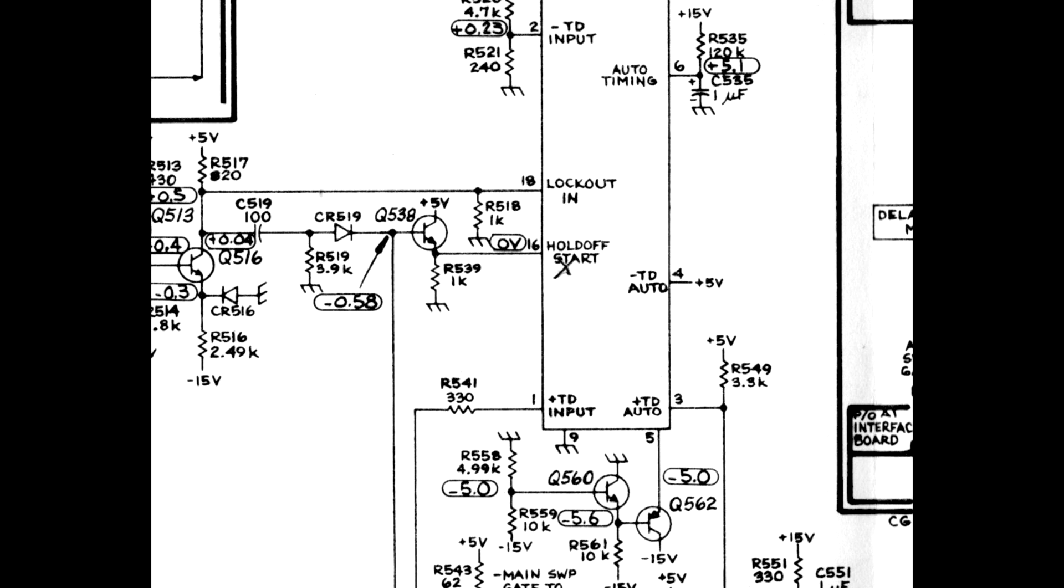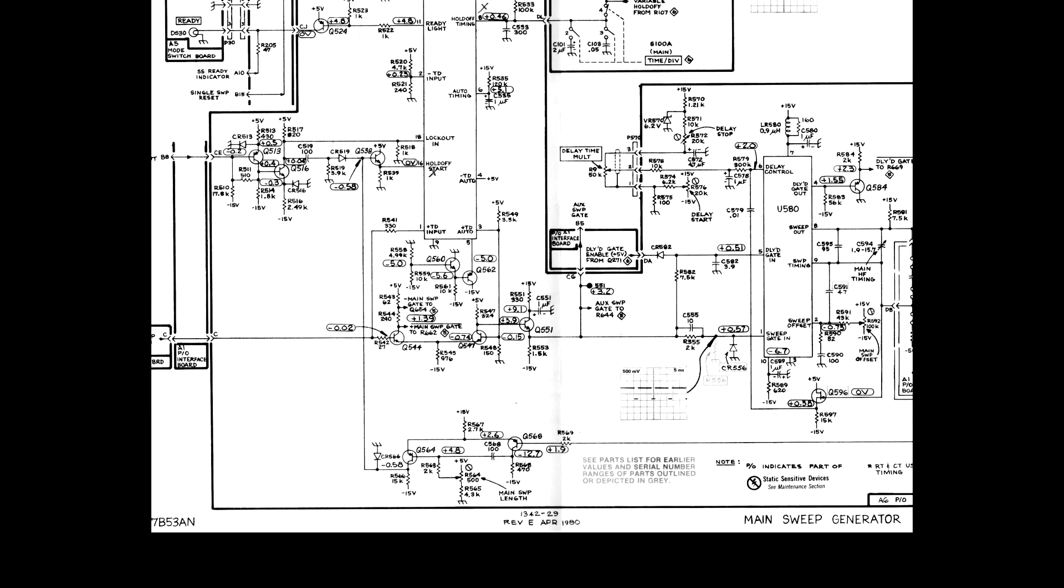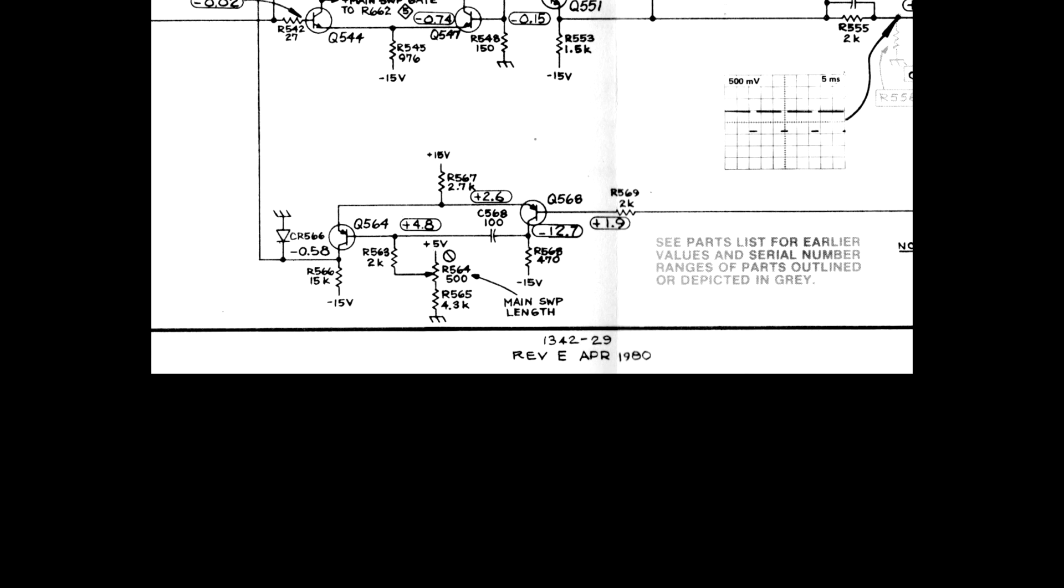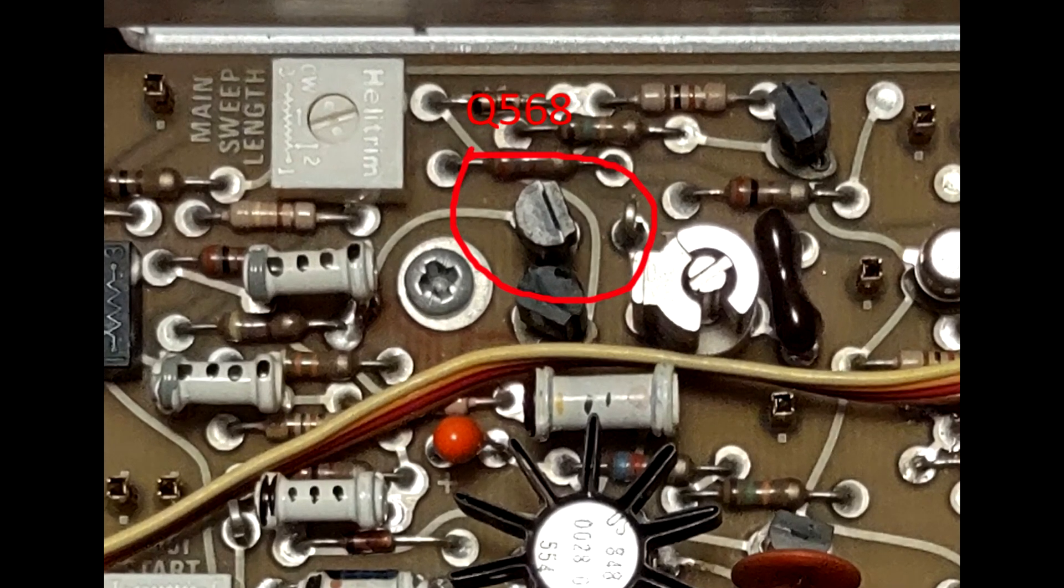Fortunately most of the transistors are socketed, so I could easily test Q538, but found it OK. Q538 is fed by Q564 and Q568, both 151-0220s. Q568 was open. Replacing the Q568 restored the plug-in to normal operation.